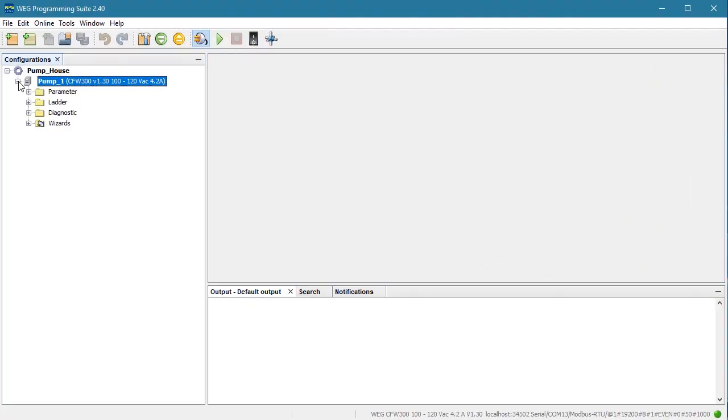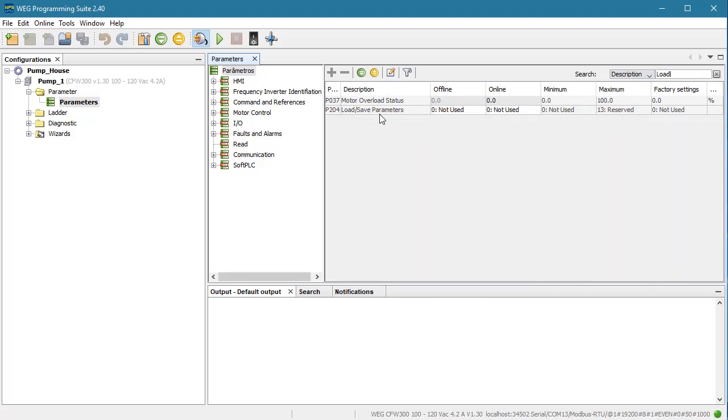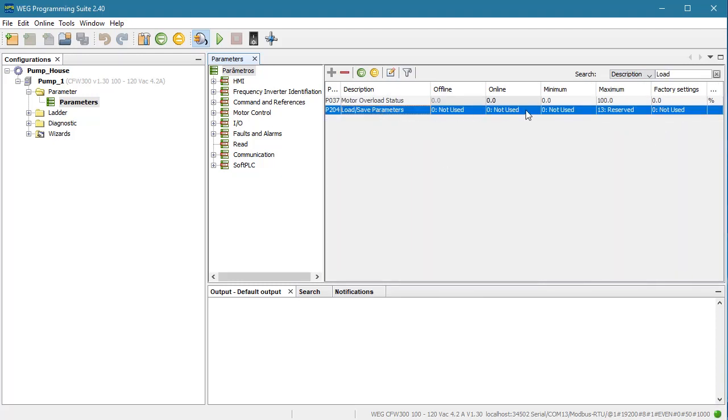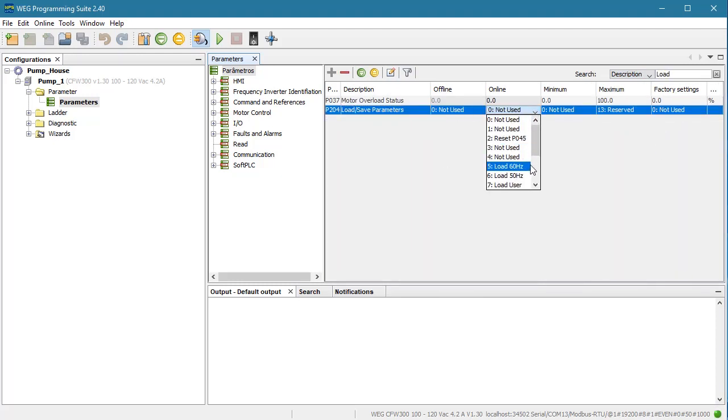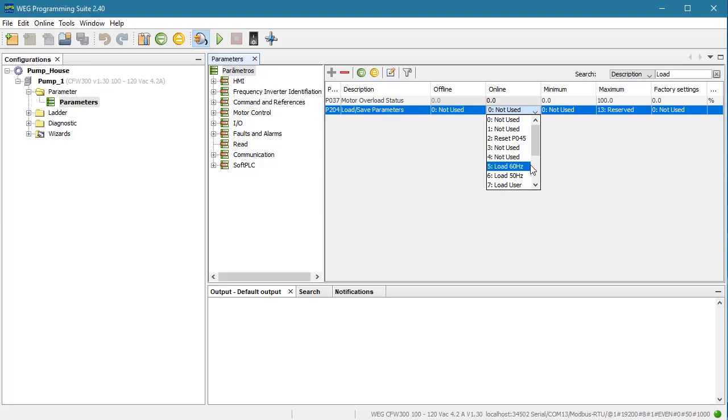Could you reset the drive from the WEG programming software? Well, technically yes. I could search for load save to find the parameter and set it to a 5. But we don't recommend resetting the drive from the WPS software. Why? Because if the software was in the middle of updating something and you issue a factory reset, there is a chance that reset could interrupt that when it power cycles the drive and leave things in an unknown state. So it's best to always do a drive reset from the drive's HMI.